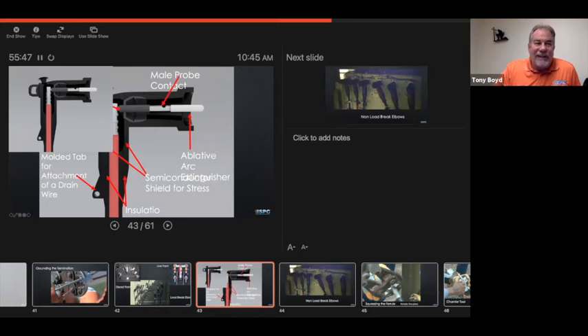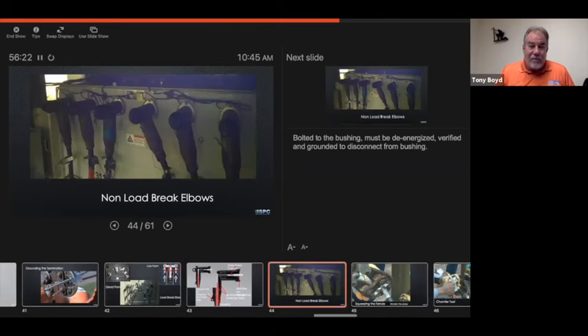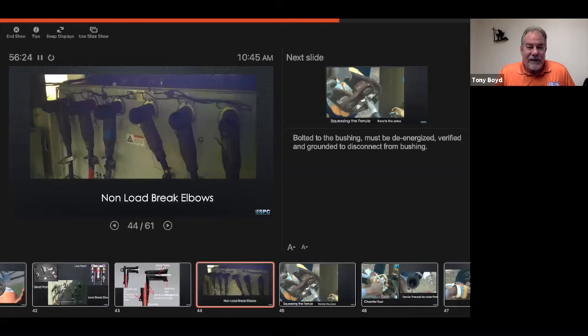It allows for bleed off from all of the current leakage coming through this elbow to try and create a safe atmosphere in case there's an inadvertent touch on that elbow from a worker. So you might have rubber gloves on. Some companies don't require rubber sleeves, so the gloves only come to the top of the elbow. If I'm working inside, my elbow may touch this elbow inadvertently while I'm working on the secondary side, and that should be bleeding off some of that wire. So that's all part of the inspections. I won't have time to get into the inspections.